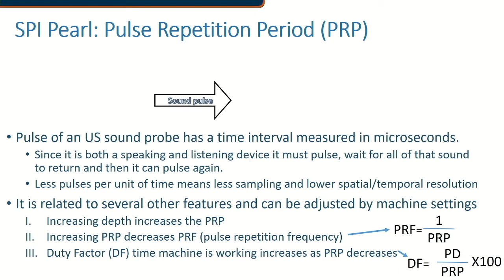Now let's talk about a specific SPI pearl, and this time we're going to talk about pulse repetition period. Your PRP is basically related to how many pulses you're going to have per unit of time, and it's measured in microseconds. And since the ultrasound machine is both a speaking and a listening device, it has to speak by pulsing out some sound waves. Then it has to listen for that to bounce off of the object and hear all those returning echoes. So you have to wait until you can send out another pulse after those first ones have returned.